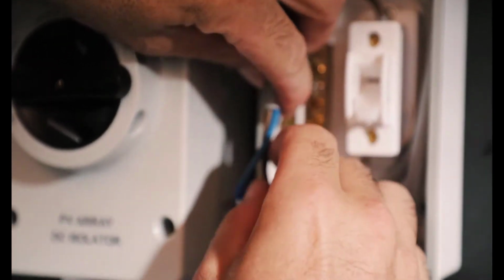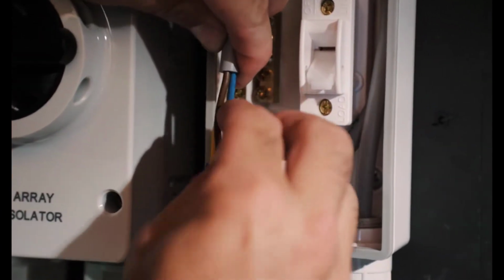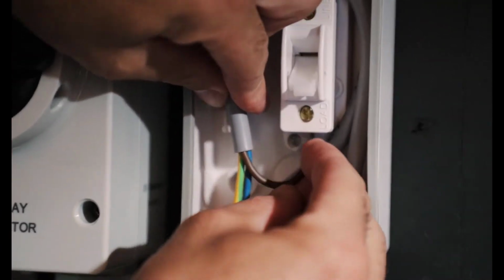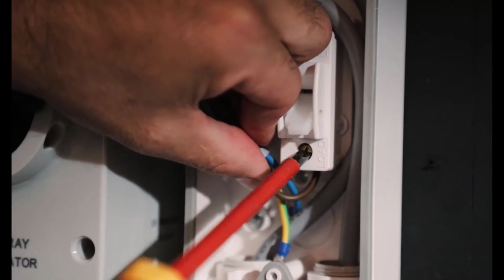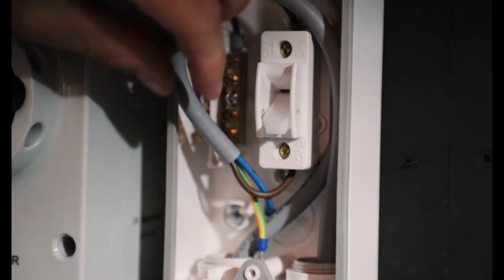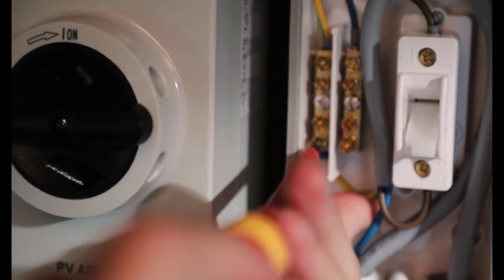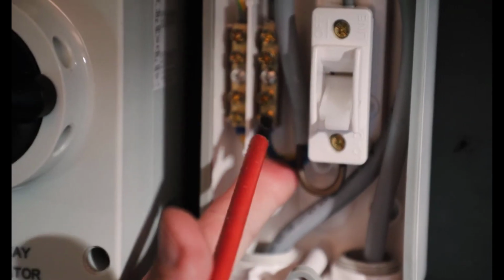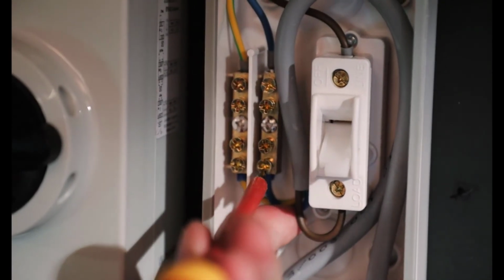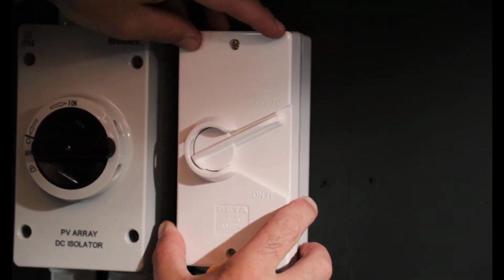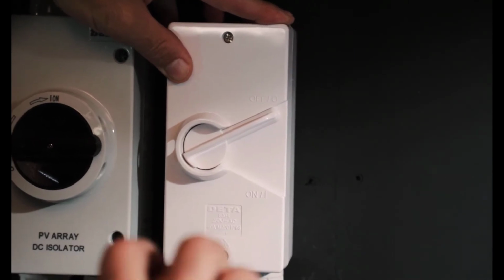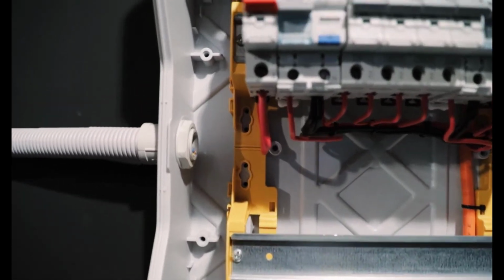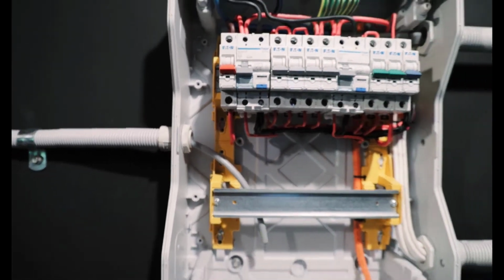Now, with all of the sonnenBatterie connections, it is very clearly stated in the installation manual the maximum run of all cables. So these have been taken into consideration, all the parameters such as voltage drop. Voltage drop is one of the most important features of the sonnenBatterie system, in that it will limit output. It will limit output of any DER, any renewable energy system, so you obviously need to take this into consideration. So here we go, AC isolator happily alongside the DC isolator, and then we bring the AC into the switchboard.